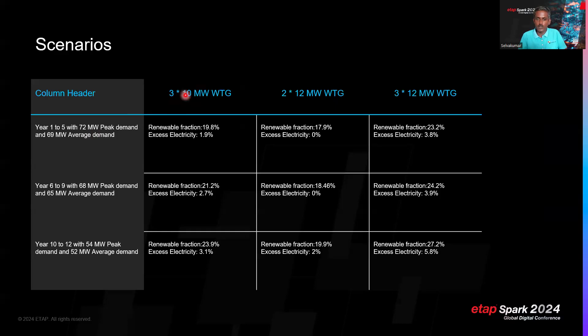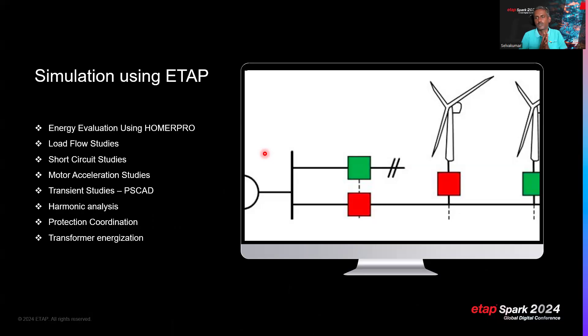Various scenarios have been evaluated: 3×10 MW wind turbine generators, 2×12 MW, and 3×12 MW configurations. The FPSO load varies over its life — years 1–5, years 6–9, and years 10–12 each have different demand profiles. For each scenario, renewable fraction, percentage of energy from renewables, and excess electricity are tabulated. This commercial and energy evaluation was performed using Homer Pro.